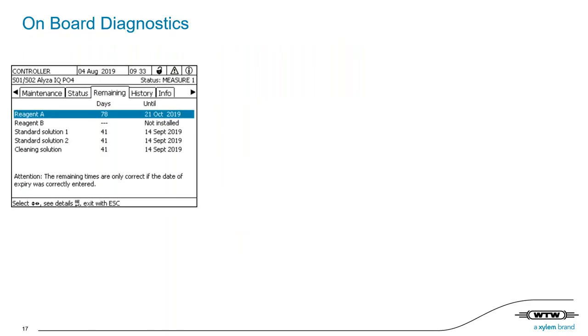As a further enhancement, we have added predictive maintenance and onboard diagnostics. The Alyza monitors the solution volumes and provides a countdown of the days remaining until you run out of solutions and need to replace it. The solution monitoring is individual to the solution, so you have a counter for the reagent, calibration solution, and cleaning solution, so you can get a complete picture of how many days of operation you have left. In addition, the multiport valve is monitored by the system and will give you a logbook notification if an exchange should take place, so that you have full transparency of the status and exchange requirements.